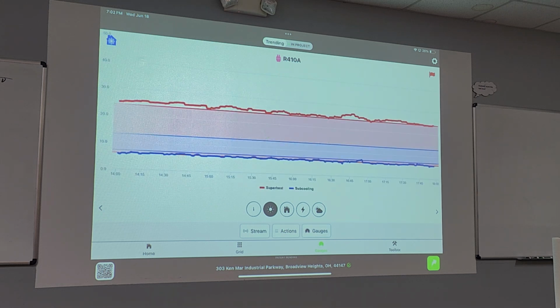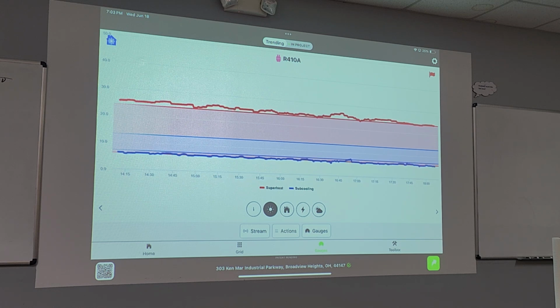Is that a degree or so? If you want to see the superheat trend, right there, that's the superheat trend. I wouldn't say the TXV is hunting a lot, really. No, it's just a degree or so. Yeah, I wouldn't call that hunting. And your subcooling's not pulsing either.